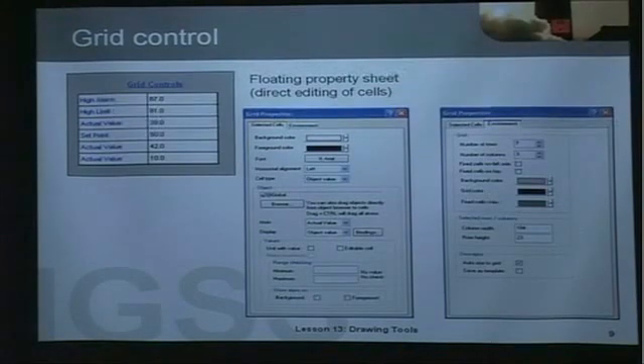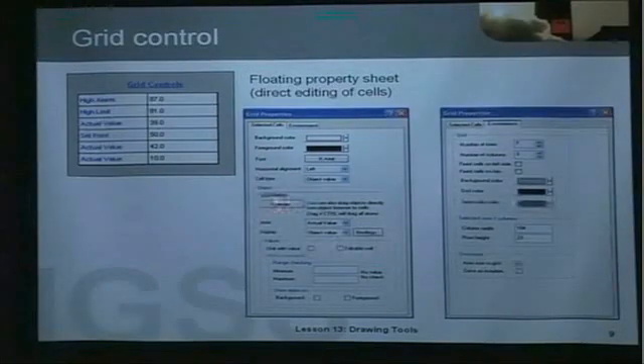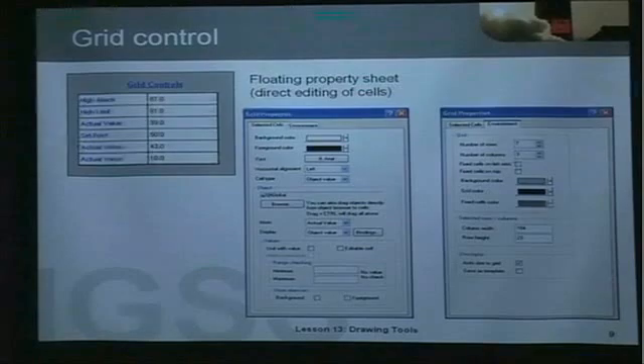Finally, we have the grid control — a very nice feature in IGSS where you can put up a table format on a diagram to collect key values from the configuration. In this example, I've collected the atoms of an analog object. You write text in the left column and link to the actual values of the configuration on the right side. This is all done in a floating property sheet where you can directly edit all the cells. For example, I've linked to object Q2 — I simply browse for my object, select the atom I want to link to, and that value is shown. This can be an incoming value, or an outgoing value where the operator, for example on the setpoint cell, will be able to send a setpoint into IGSS.